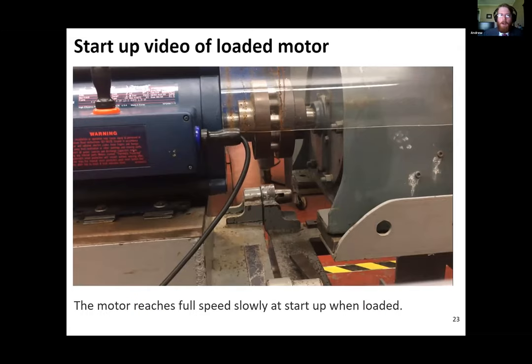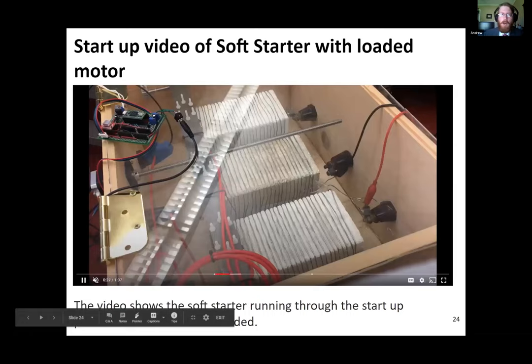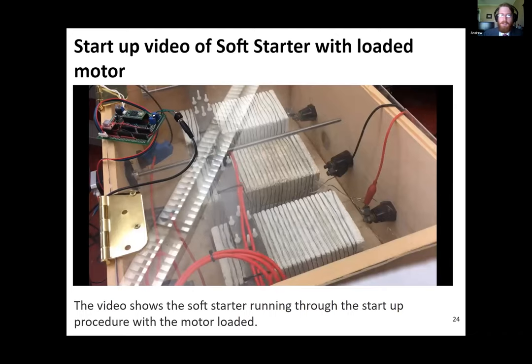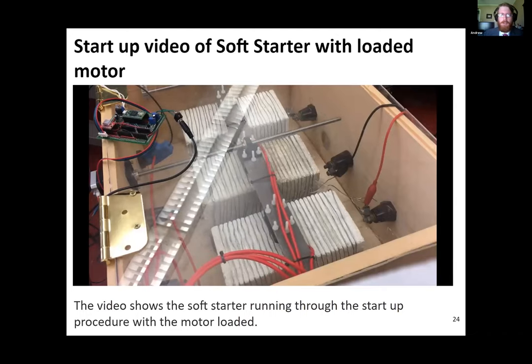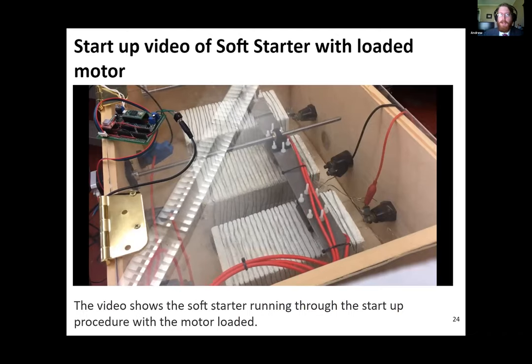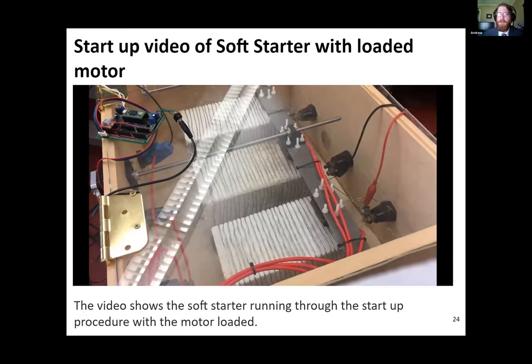These next few videos show the test that we performed for the dynamometer loaded motor in the lab. The response time was about 15 seconds for full acceleration versus 10 seconds for the unassisted acceleration. Like we said, we managed to get our 15 amp inrush current reduction. On the next video, we can see the internals of the machine during the same test, as it goes all the way from the maximum resistance to the lowest resistance. For all the testing, we simply had the wiper bar cycle all the way through both directions, just so that we could see the performance going up and coming down from it.